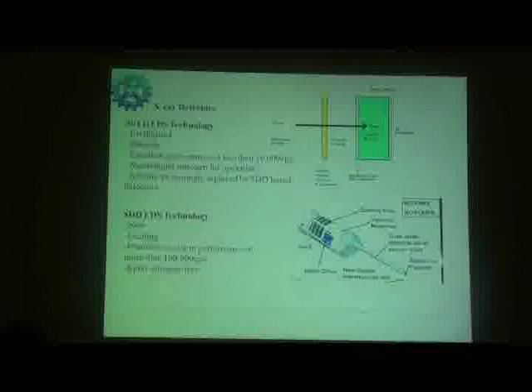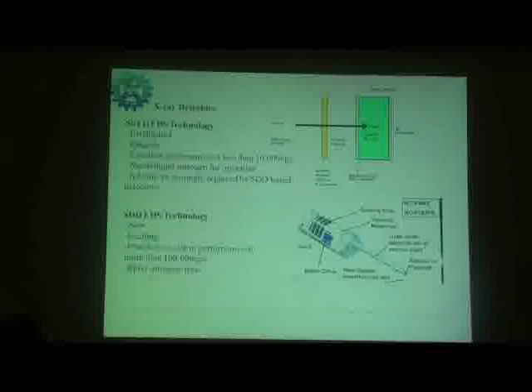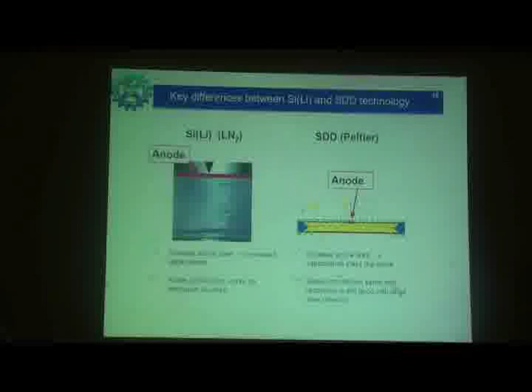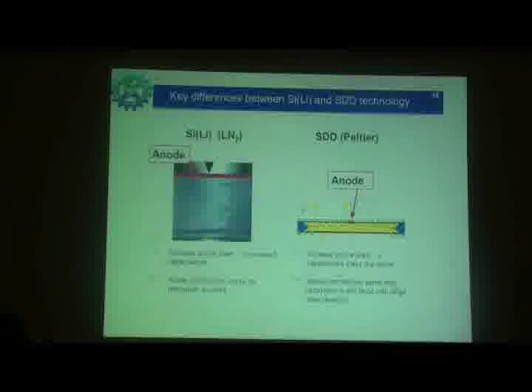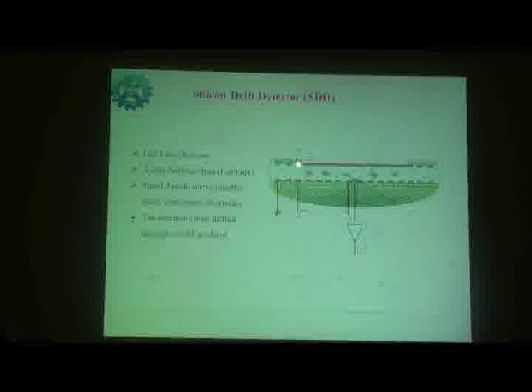And the latest technology, the silicon drift detector, is made on a similar principle, but you don't have the problem of lithium. Concentric electrodes are made over the anode, and by these you can create gradients very slowly towards the anode, and the electrons, whatever cloud is formed, I will just show you. So this technology doesn't require any liquid nitrogen. You can get very high counts and excellent performance. This is the modern technology which doesn't require LN2. Normally LN2 is very cumbersome to get sometimes when the source is not near your place.